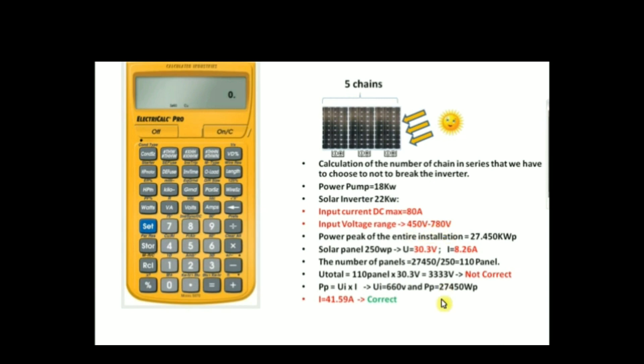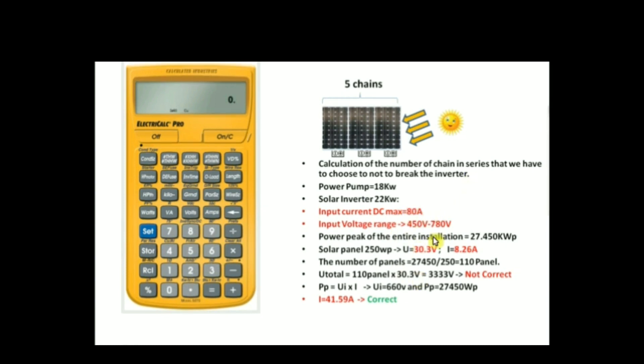As a solution, we choose a voltage to deliver to the inverter that must be within the valid range of 450 volts to 780 volts. We're going to choose 660 volts — you can choose any value within this range. You also have to watch the input DC current delivered to the inverter, which must not exceed 80 amps.